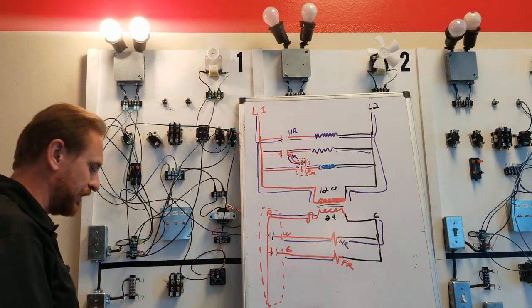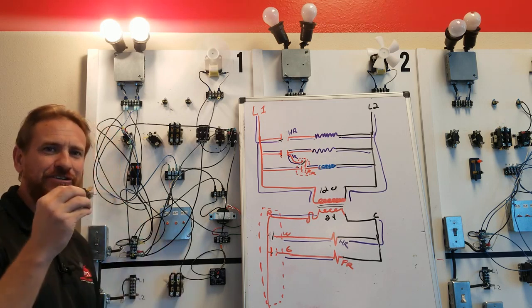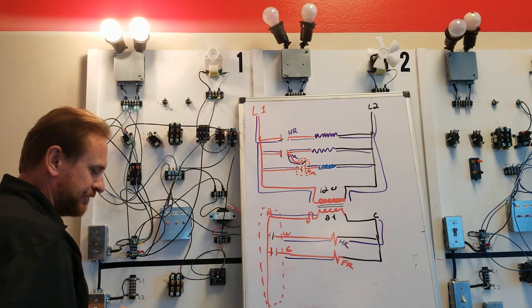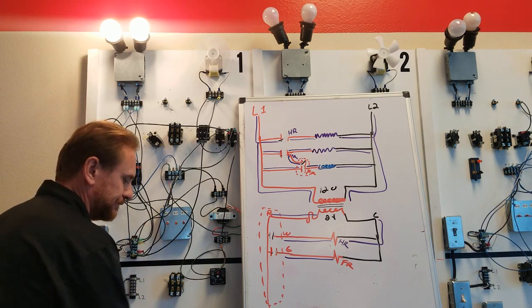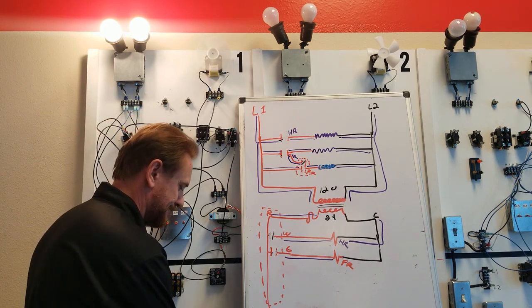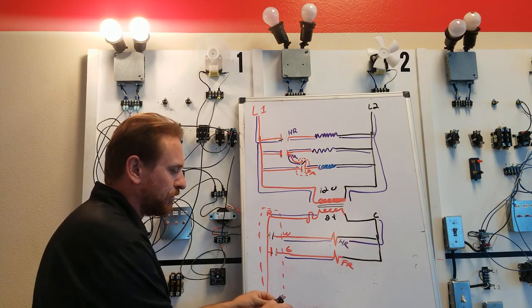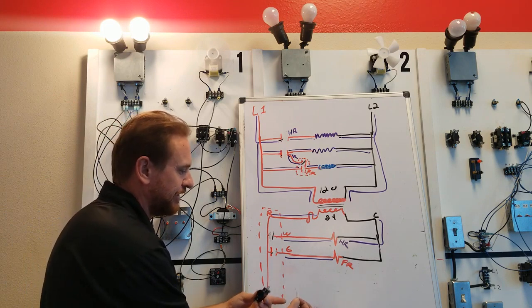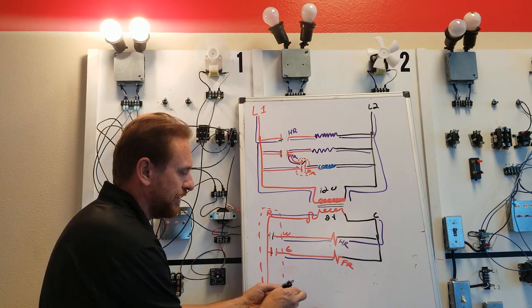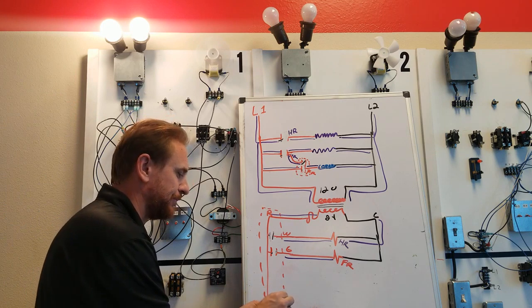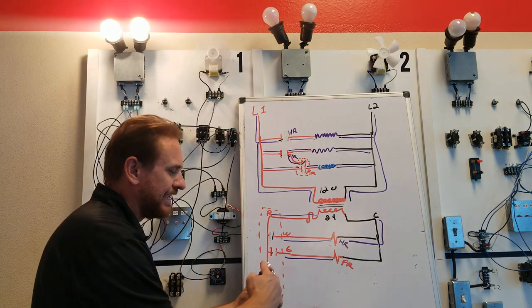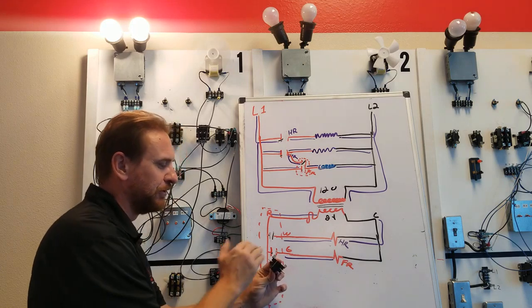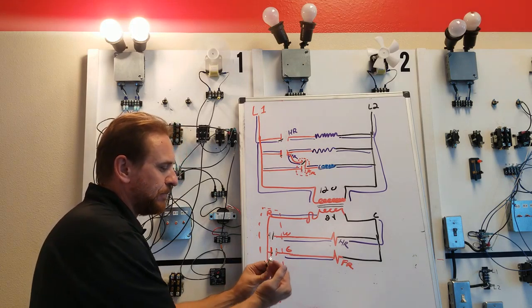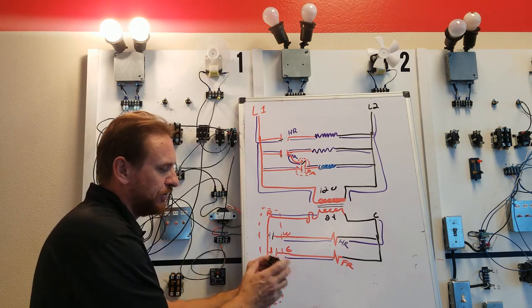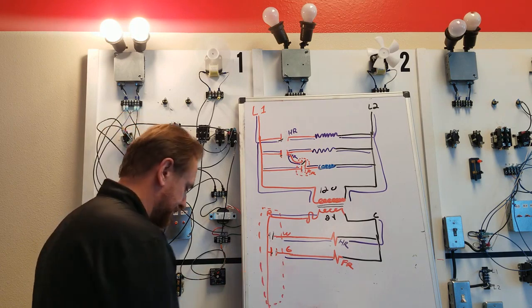So this part here is a switch. How it works, there's a little heater in the low voltage side. And there's a piece of bimetal that keeps these switches open. Let me explain this. We have these two little porcelain rods right here, and they're white. It's going to be hard to see with the background, but these two porcelain rods keep this switch opened up. These two separate switches opened up. So they keep this open, and they keep this one open, so no electrons can pass. When this bimetal pops down, this switch closes here, and it closes here.